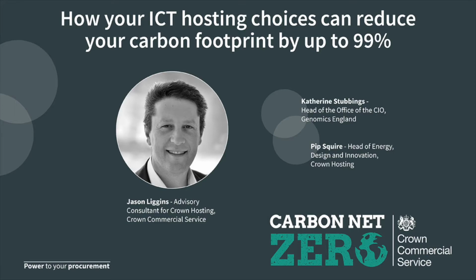In terms of efficiency, server rooms are the least efficient. For every 100 kilowatts of power used by the IT systems, the facilities probably need more than 300 kilowatts of supporting load, what we'd call parasitic load. And that would give a PUE, a power usage effectiveness, of 4. That's 4 times the amount of power.